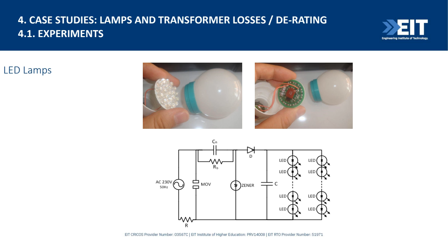So we did experiments to measure the current and voltage waveforms for CFLs and LEDs. As you can see here, one thing is very obvious. For CFL lamps, if you look at the current waveform, you can see very sharp points here. It means that we have higher harmonics in CFL lamps. And if you look at the LEDs here, we do have some sharp points, but they're not as sharp as those for CFLs. So it's telling us experimentally that CFLs are generating more harmonics, so they might more effectively affect our transformers' efficiency. And you'll see what happens.